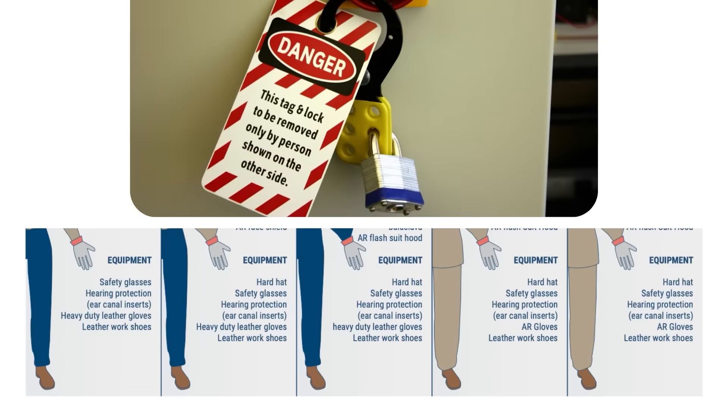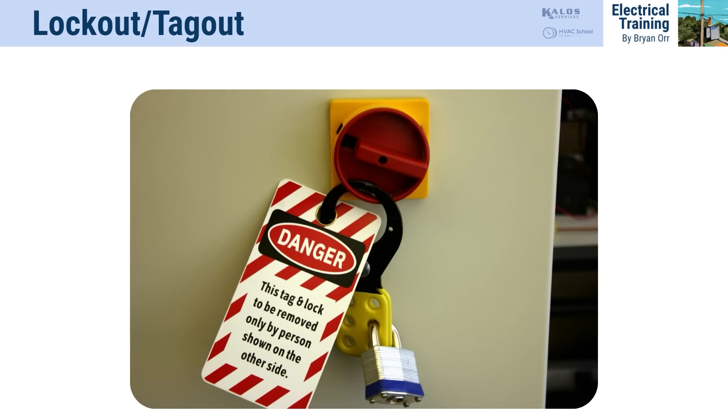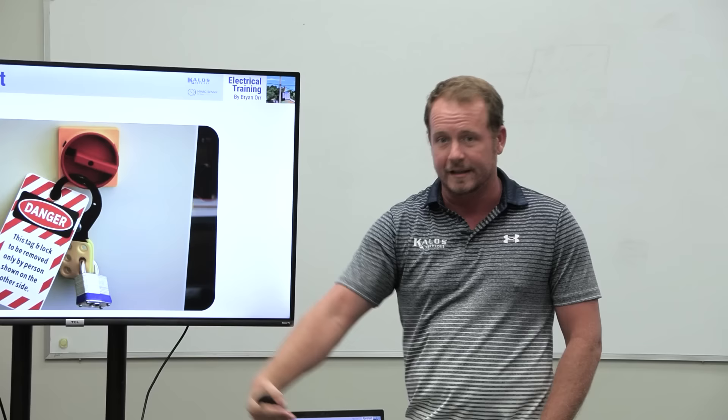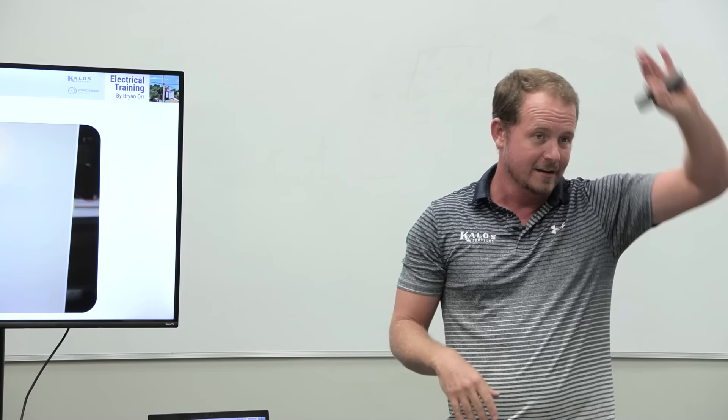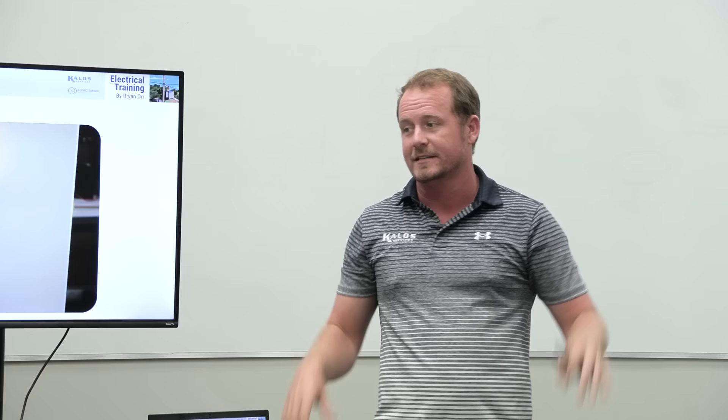Lockout/tagout: any time you're working on equipment that has the potential to be re-energized while you're working on it—and the switchgear is not directly under your control—you need to lock it out and tag it out. If I shut a disconnect off and it's right there next to me, I don't need to lock it out. But if what I'm working on is on the incoming side of a disconnect and the breaker is in a motor room on the other side of the building, I need to lock and tag that out so I'm the only one who can turn it back on.